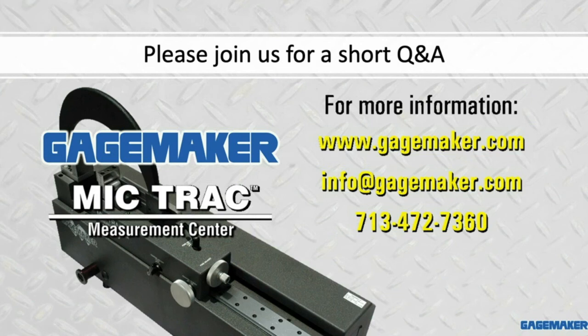We do have more coming in, so let's just keep on going. Okay. Does the TRAC have an associated software system that creates a calibration report when calibrating in-house? Yeah, so I think what he's meaning there is a calibration report or a calibration certificate. So the software associated with a TRAC, that's the software we designed, called Certify. And Certify automatically comes with a TRAC 4000 series, and then it's available as an upgrade for a TRAC 3000 series. That software basically lets the TRAC talk to the computer instead of a digital readout. So when you're taking readings, they automatically populate in the tables, and they generate a cert.